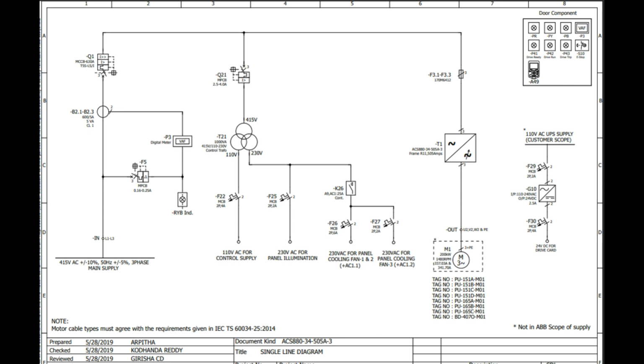Next, if you go ahead you can see K26, that is the contactor, and this is further tapped into two different MCBs and both are used for panel cooling fans, F26 and F27. So this is the job of the control transformer, to divide the voltage, and the rating you can see for the control transformer is 1000 VA or 1 kVA.